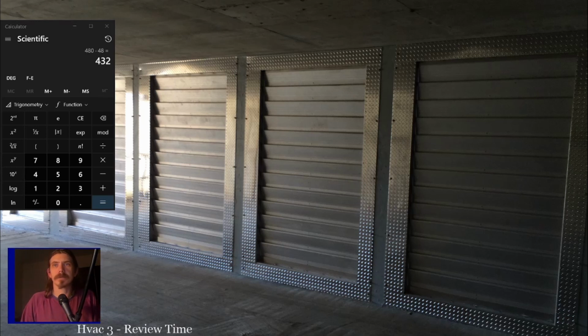solenoid valves, relays, anything that has a coil essentially is going to end up being an inductive load. I don't want to say coil because people think of heat coils as heat coils, right? But anything that creates a magnetic field is going to be an inductive load. Anything that's a straight resistance, like heaters and stuff like that, that's a resistive load.